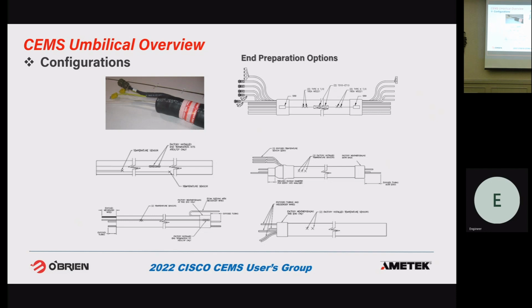We can also do both ends. What I tell customers, if they want both ends factory sealed, I only recommend that if it's a shorter line, or you're replacing a line you've taken down and been able to do an exact measurement. Because if you order a 250-foot line, we've prepped both ends, you install it, and it's really only 230 feet, you're cutting off some of that work you paid for. So I recommend, if you want an end finished, just do the shelter or power end, and cut any excess off the other end.